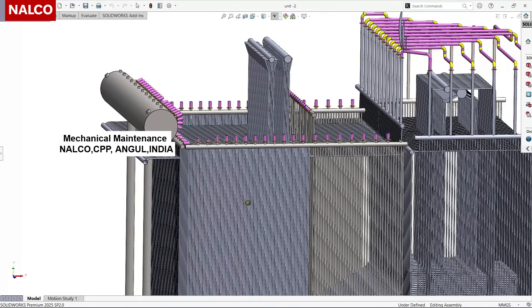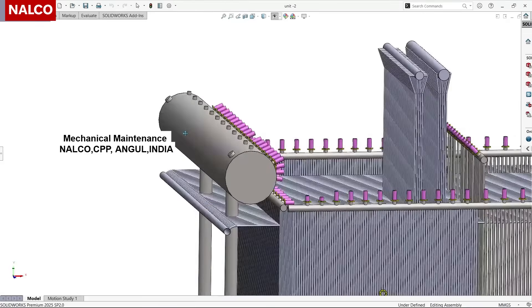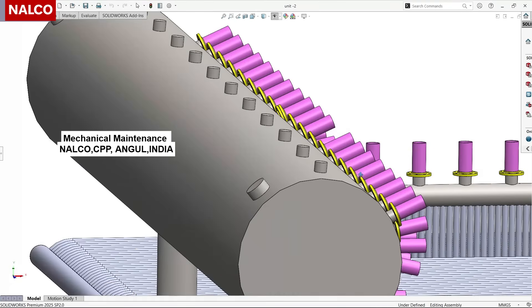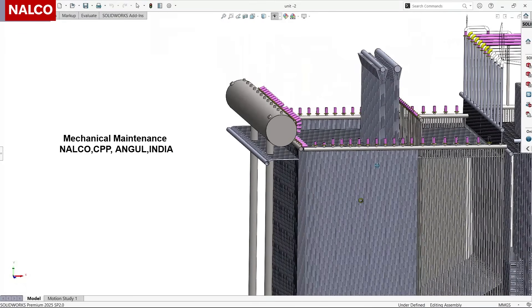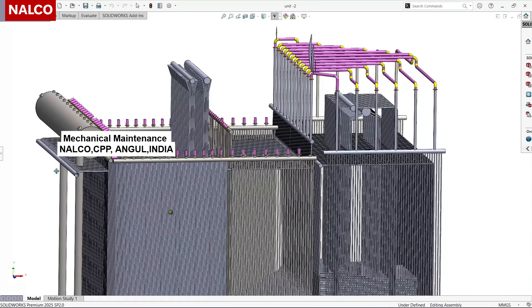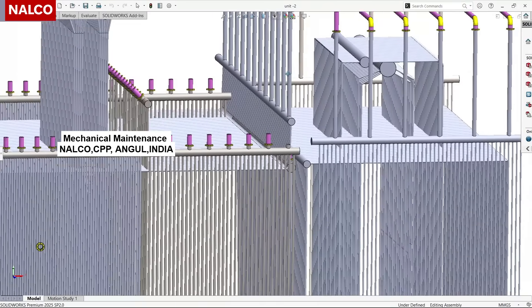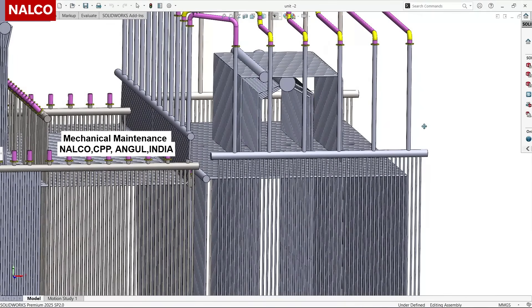From inside the steam drum there are turbo separators which separate the saturated steam from water. The saturated steam goes from these tubes into a header called super heater header one. From super heater header one, an array of tubes takes it to super heater header two, and then it gets split into three right and three left.